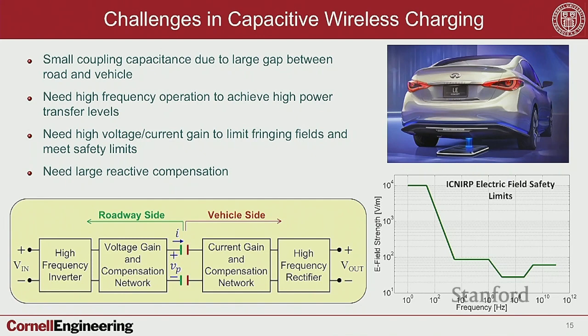The first thing we needed was a system that provided voltage gain. Essentially, we come off a DC voltage and invert that into a high frequency using an inverter. This voltage is still at a few hundred volts because our DC voltage comes off the line and gets rectified, so it's a few hundred volts. Then we boost this up into the kilovolt level, transfer the energy, and convert it back into the voltage levels needed for a battery.